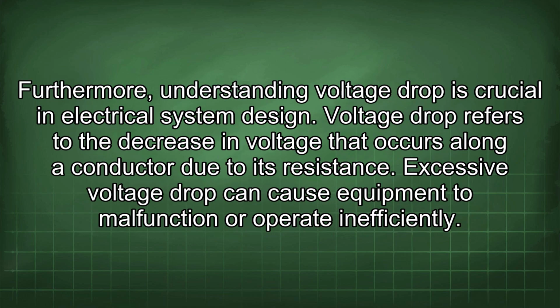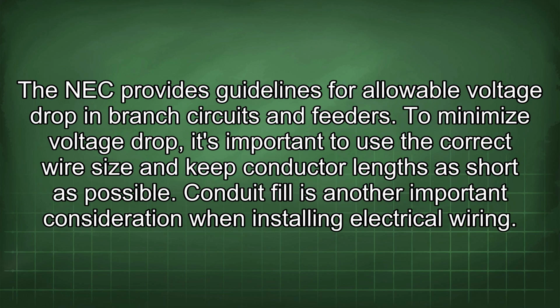Furthermore, understanding voltage drop is crucial in electrical system design. Voltage drop refers to the decrease in voltage that occurs along a conductor due to its resistance. Excessive voltage drop can cause equipment to malfunction or operate inefficiently. The NEC provides guidelines for allowable voltage drop in branch circuits and feeders. To minimize voltage drop, it's important to use the correct wire size and keep conductor lengths as short as possible.